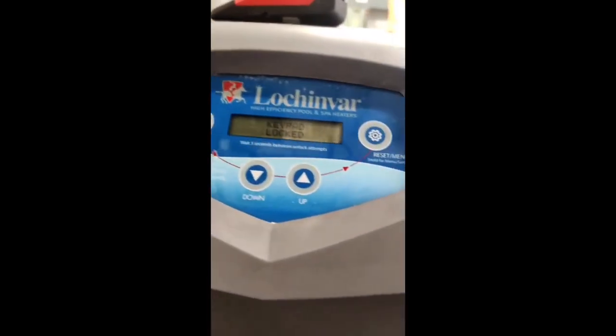I know what that is, but the part that is confusing, it says water pressure switch, and then it says auxiliary device 1, and that's the lockout I got. But the switch that I replaced, it senses the pressure of the water, so why would it be auxiliary device 1? That is water pressure switch and auxiliary device 1. It almost makes me think it's the same thing, but I don't know, because that's the code I got, which I don't know if this really fixed the problem or not. I'm gonna know in due time.